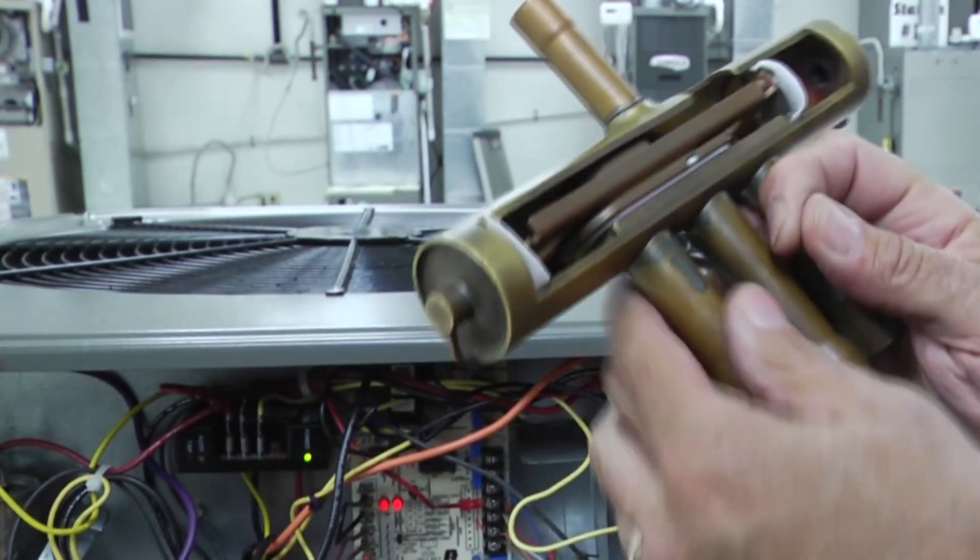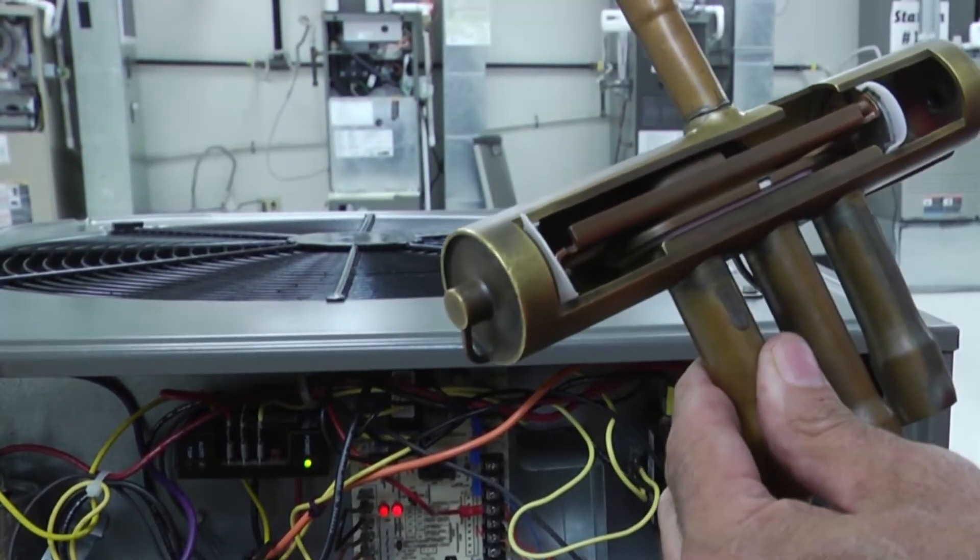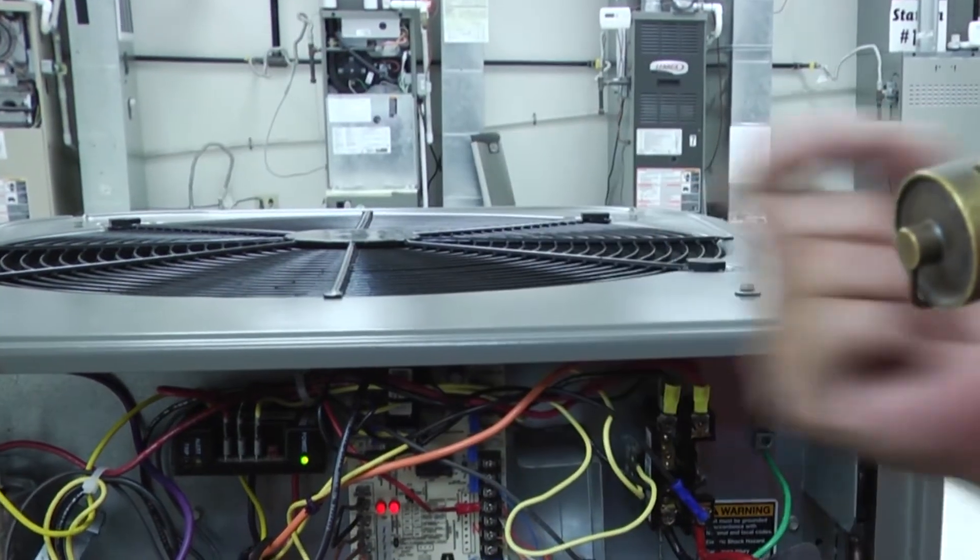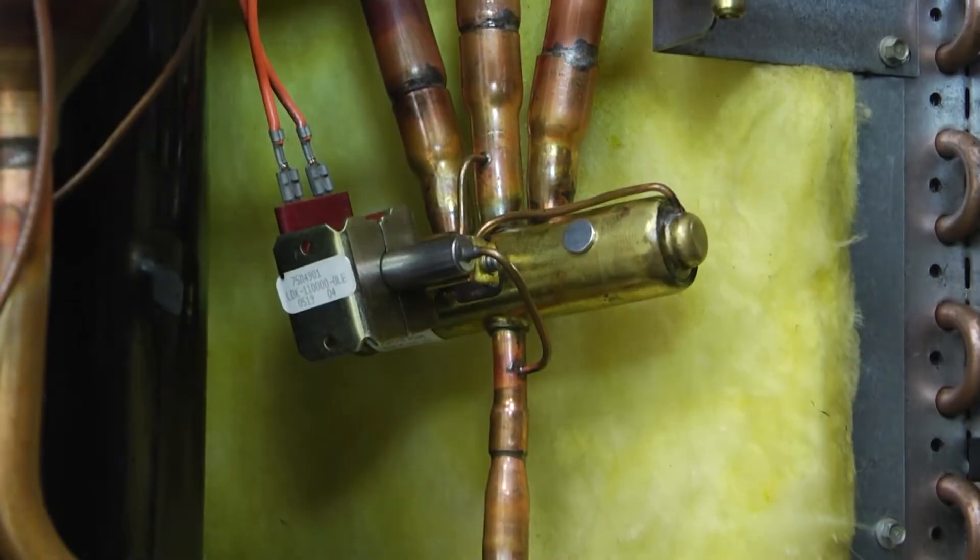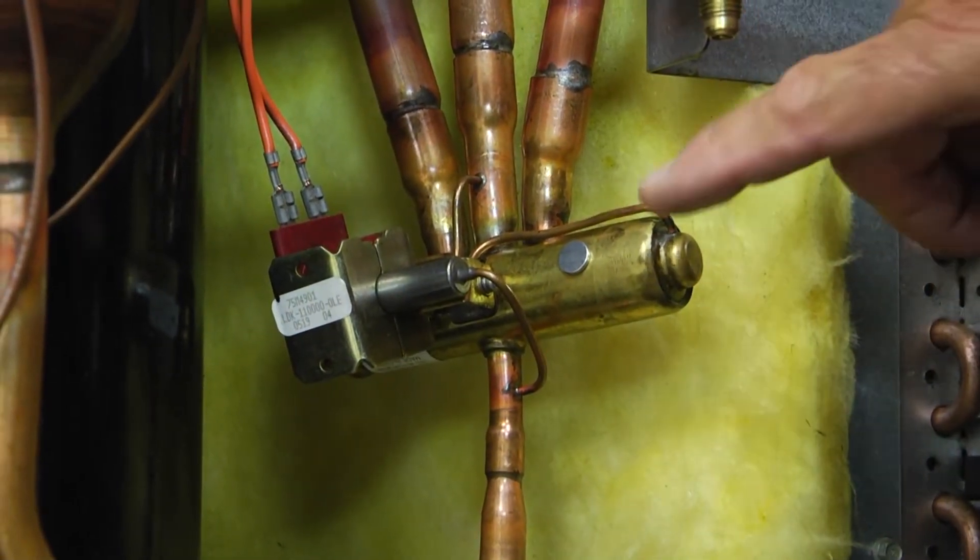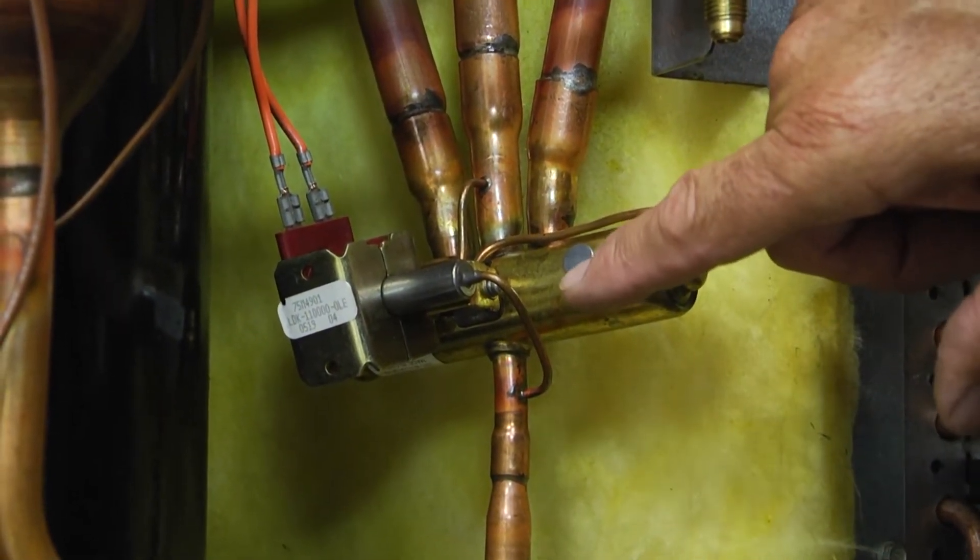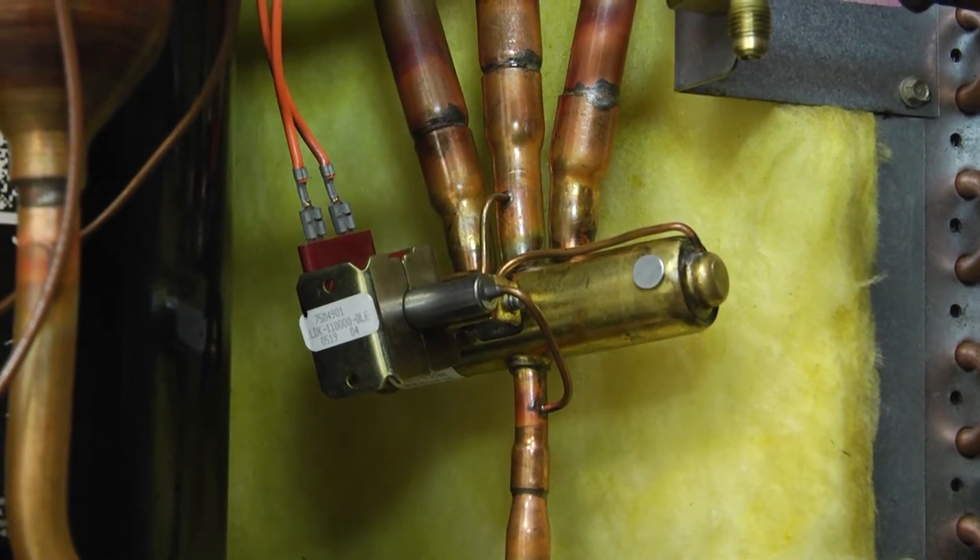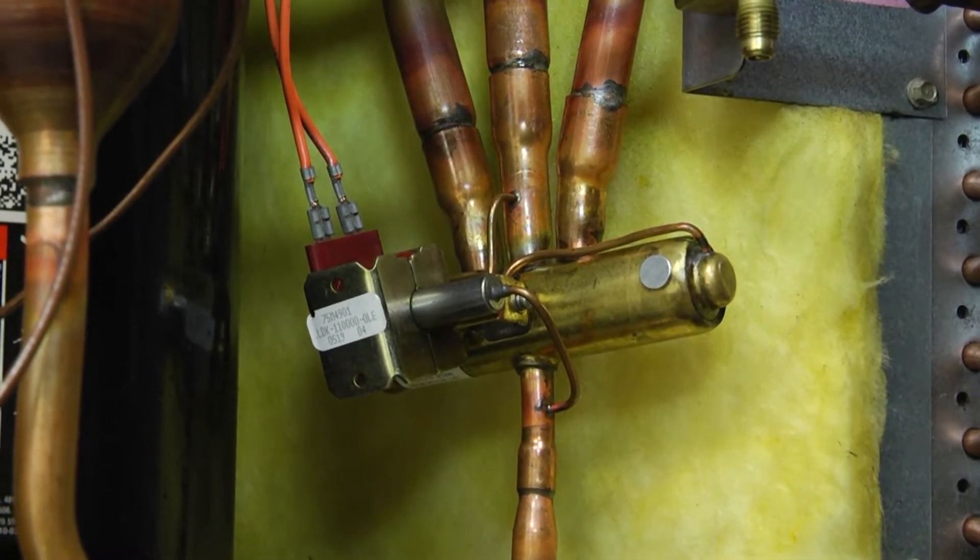So, what we'll do is now go to the live unit, put the magnet on it, and we're going to be able to watch it shift back and forth. So, this unit is running. We've got our magnet on our reversing valve. We're going to shift this to heating, and you can watch that magnet go back and forth.